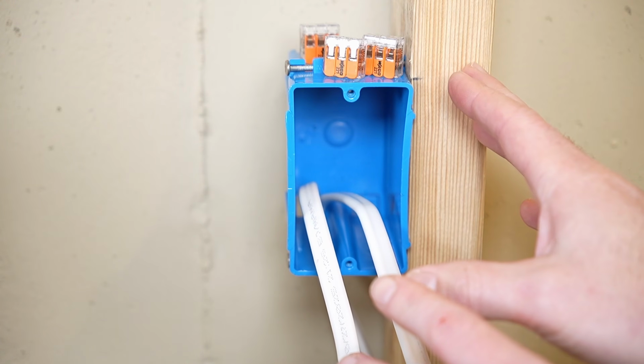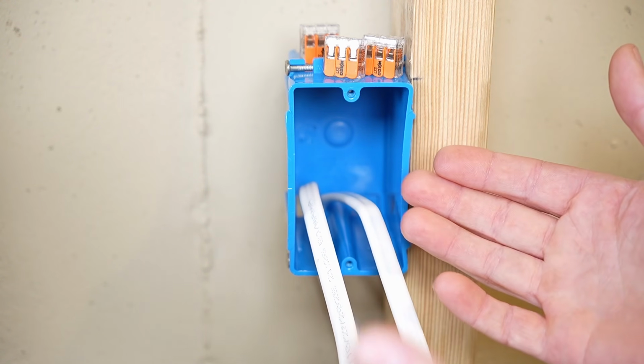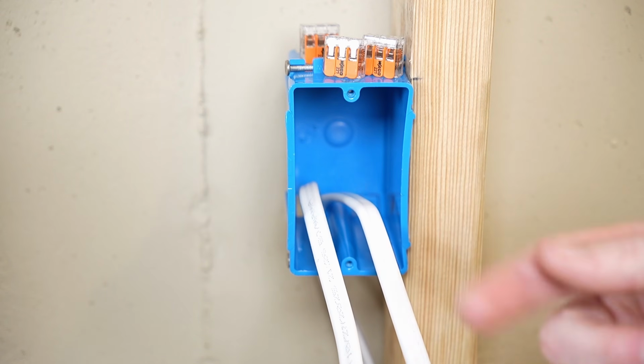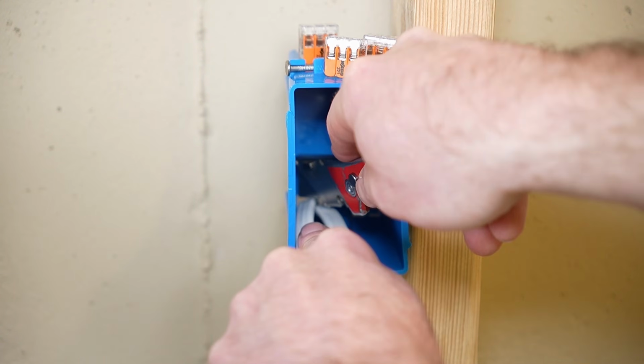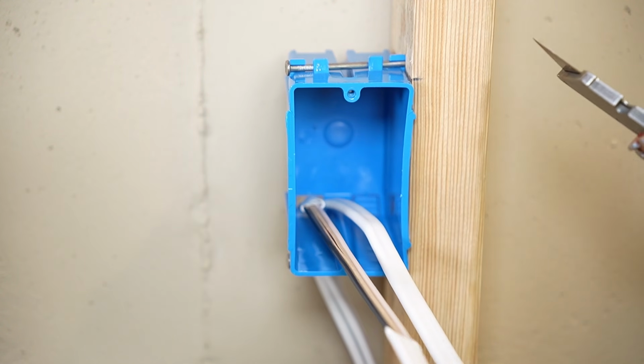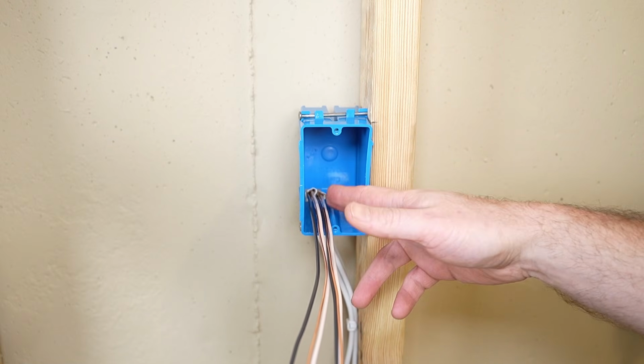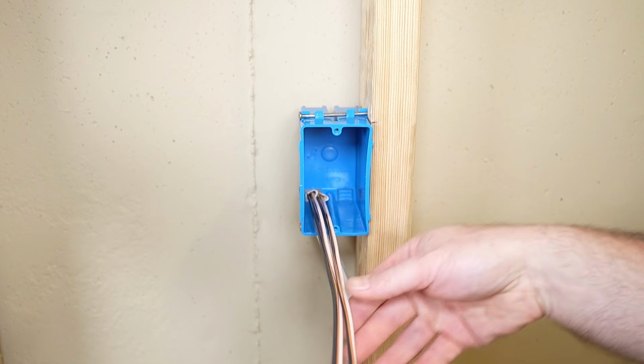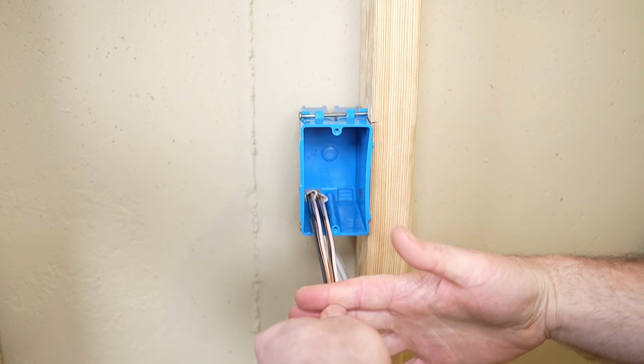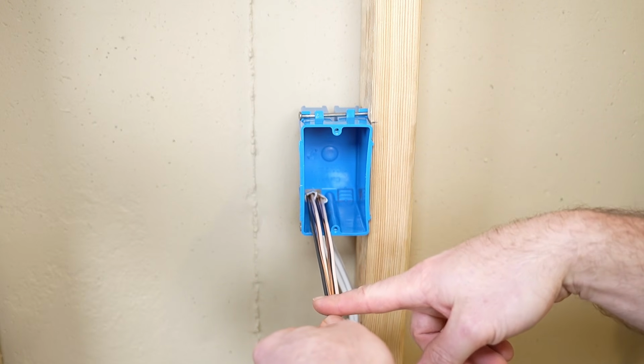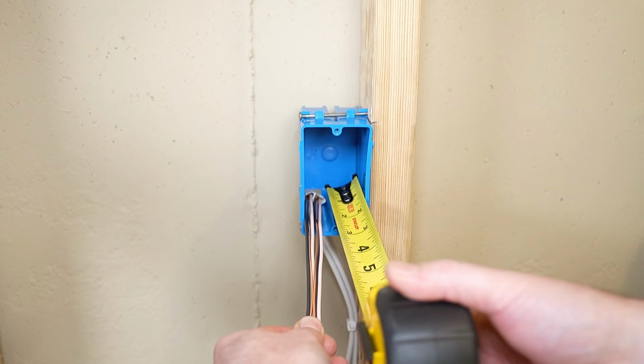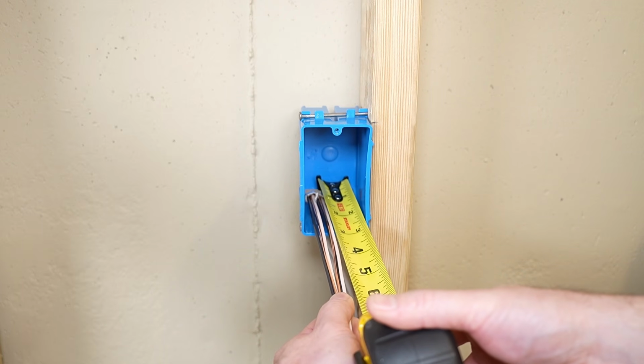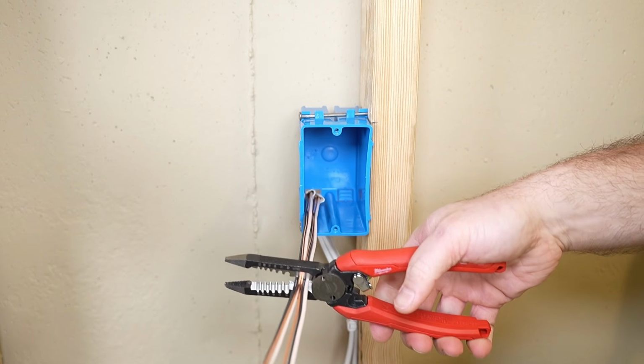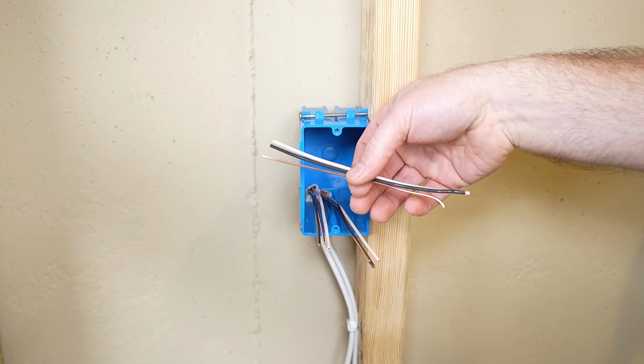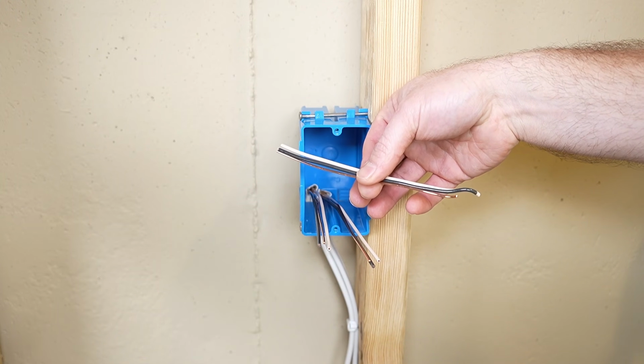The principle for this box is going to be the same. We're going to have to get everything stripped out, and we're going to have to make a set of pigtails so we can jumper to the receptacle once we get to that phase. First step is to strip out the Romex cable, or the NM. Great, now we've got our cable sheath stripped out and all of our conductors exposed. Now we need to cut these conductors down to 6 inches from where they enter the box. So again, just for the sake of seeing this on camera, that would be roughly right here. So I'm going to go ahead and cut all of the cables right here, and I'm going to use the longest set of these scraps as my pigtails.